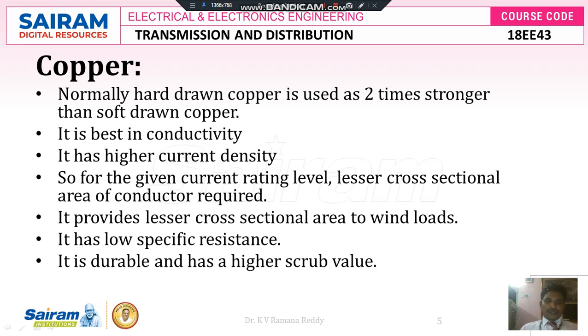Copper has higher current density, meaning it can transfer a high amount of current. For a given current rating, a lesser cross-sectional area of conductor is required, which also provides less exposure to wind loads. Copper has low specific resistance — from the formula R = ρL/A, the value of ρ is very low for copper. It is also durable and has a high scrap value, meaning it has higher reliability and can withstand mechanical stress during installation and connections.